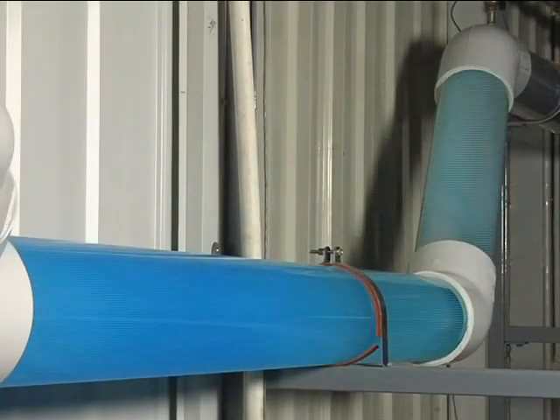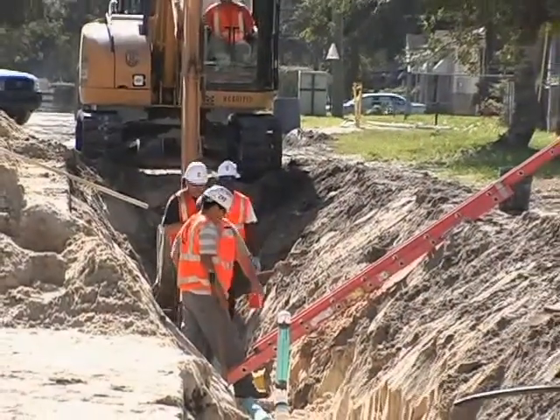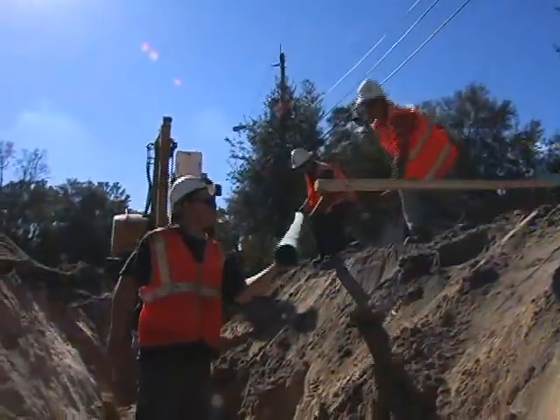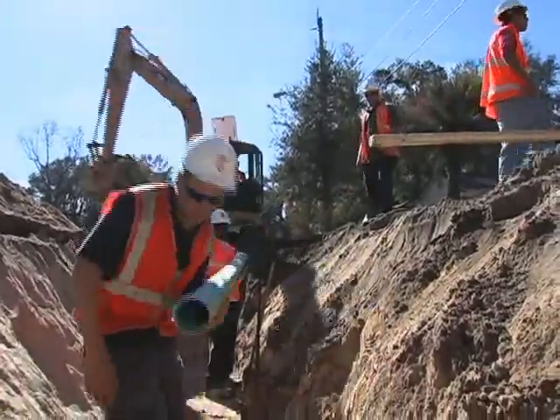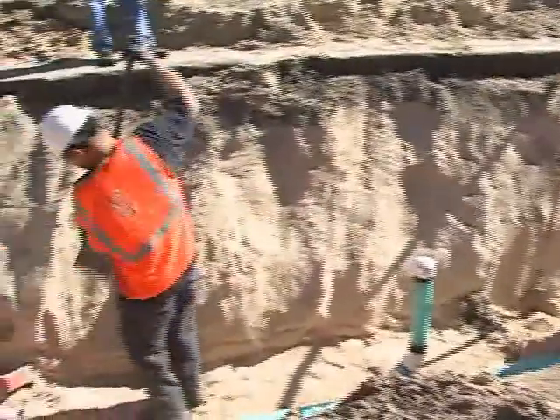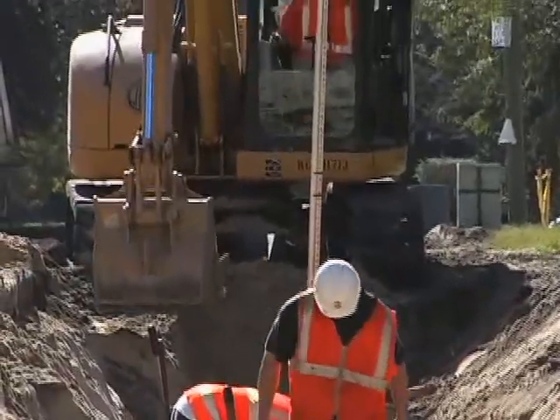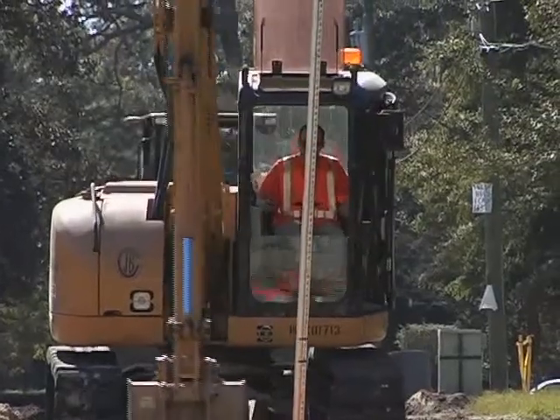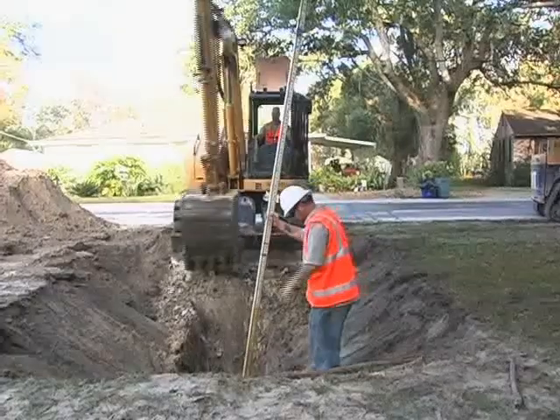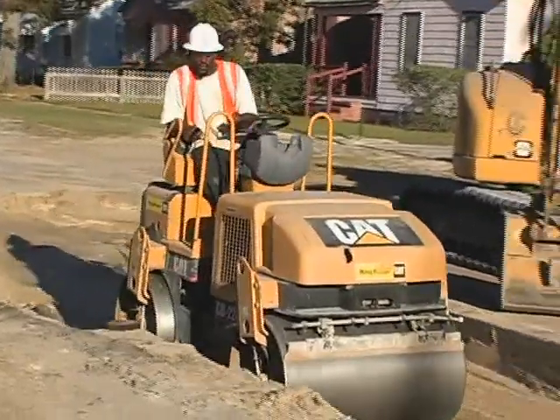Because of the pressure differential, flow can be uphill as well as downhill. Vacuum pipe installation is relatively easy and cost effective. Vacuum mains, which are typically 4, 6, 8, and 10 inch SDR21 PVC pipe, can be buried in shallow trenches, usually about 3 to 5 feet deep. This means less excavation, fewer pieces of heavy equipment, and less disruption of traffic, business, and services. Vacuum mains also provide excellent installation flexibility — the mains can easily be diverted around buried obstacles without expensive and troublesome change orders.